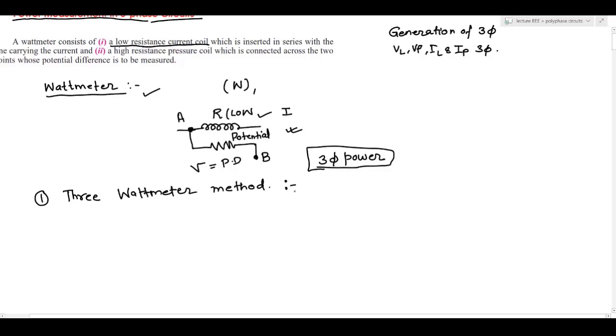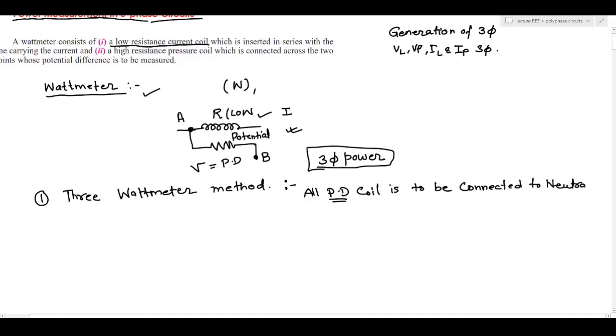We require three wattmeters for measuring the power. The problem with the three wattmeter method is that all the potential coils need to be connected to neutral. We have to connect them to neutral, so we need to identify the neutral point.